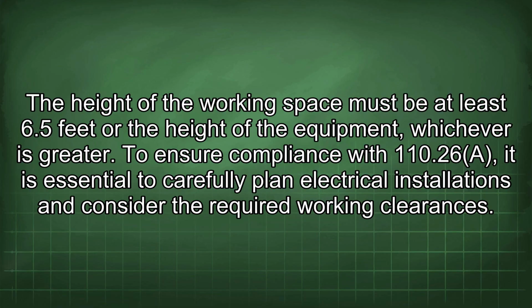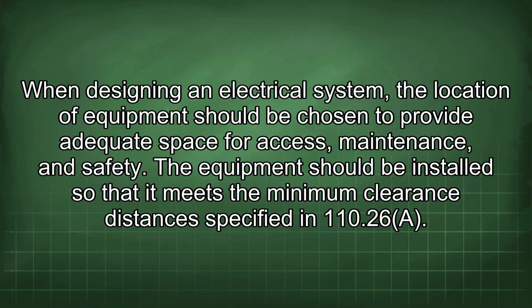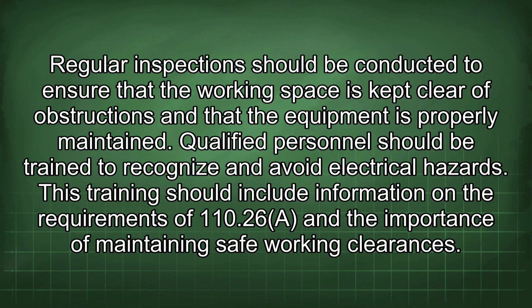To ensure compliance with 110.26(A), it is essential to carefully plan electrical installations and consider the required working clearances. When designing an electrical system, the location of equipment should be chosen to provide adequate space for access, maintenance, and safety. The equipment should be installed so that it meets the minimum clearance distances specified in 110.26(A). Regular inspections should be conducted to ensure that the working space is kept clear of obstructions and that the equipment is properly maintained. Qualified personnel should be trained to recognize and avoid electrical hazards. This training should include information on the requirements of 110.26 and the importance of maintaining safe working clearances.